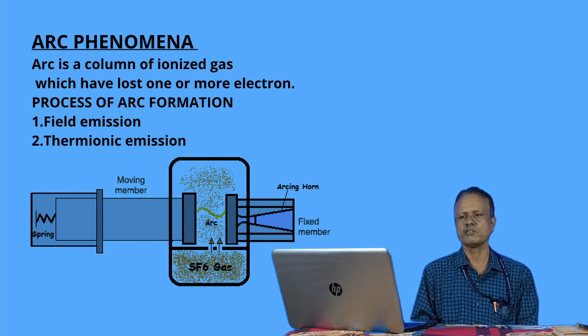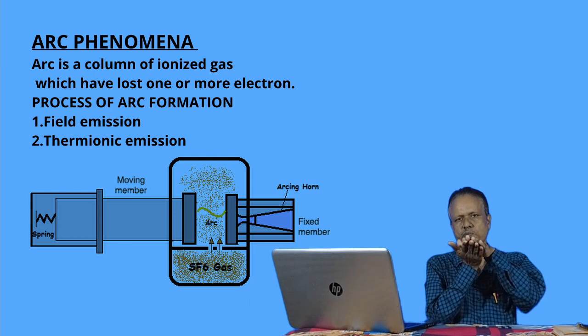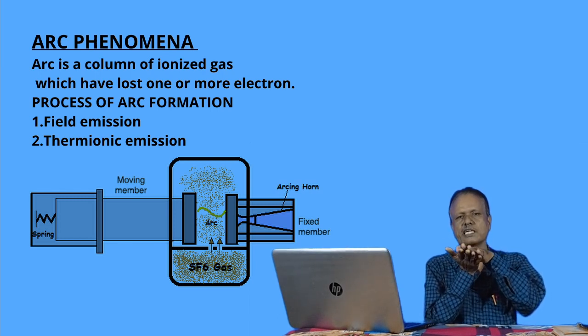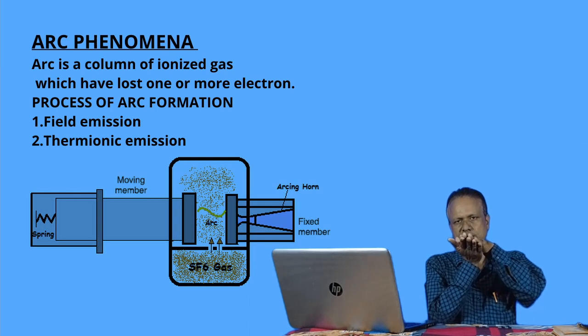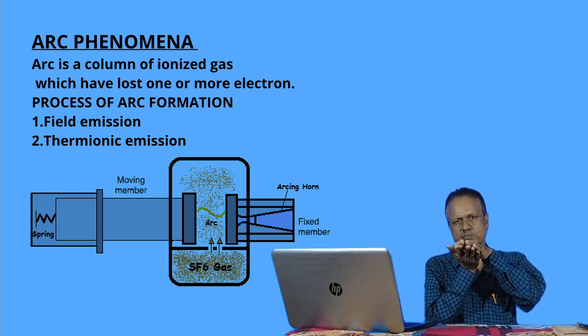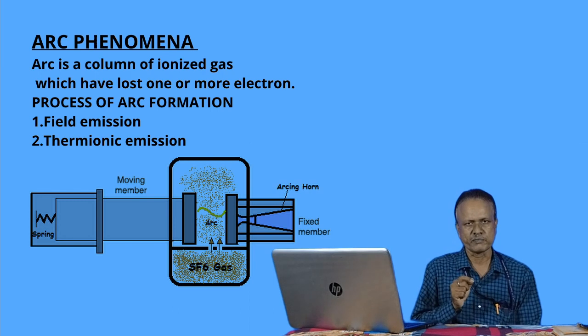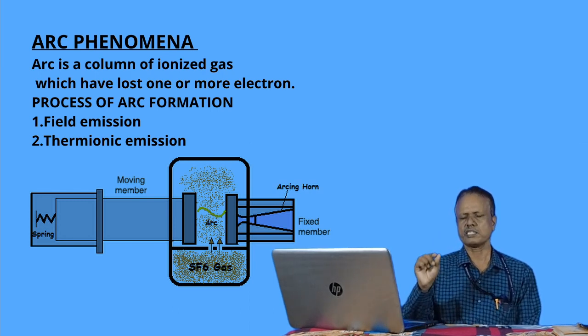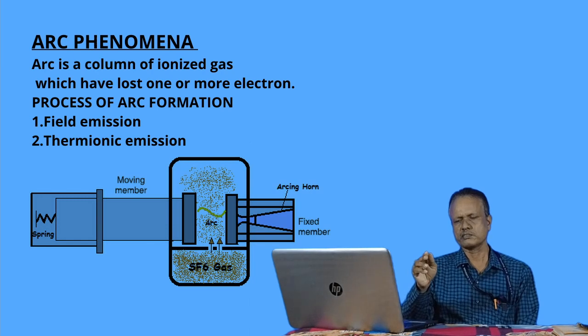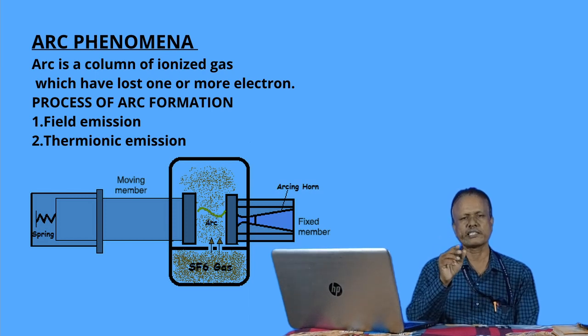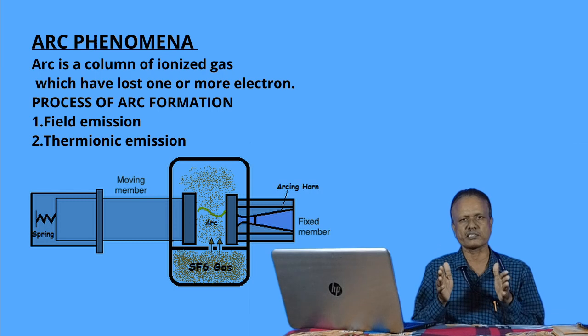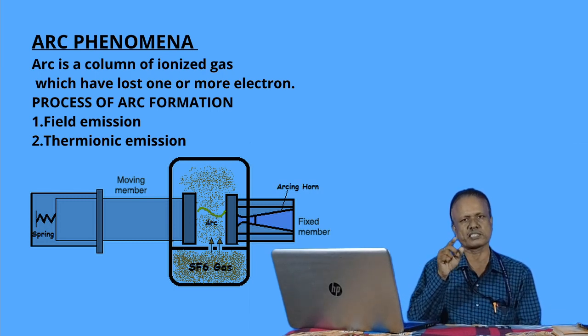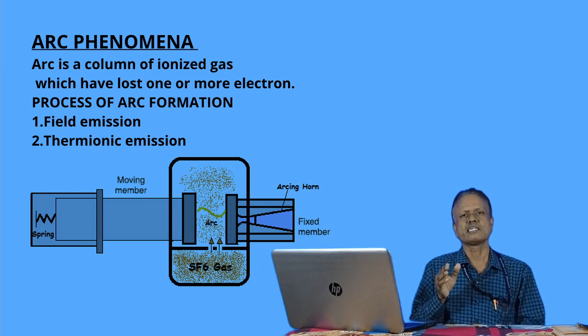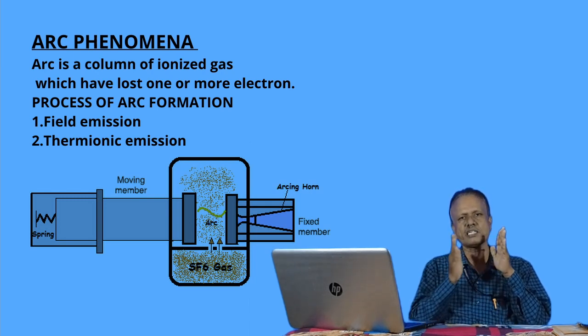In this field emission we observe that when the moving contact gets separated from the fixed contact, the contact area gets reduced, and at that time due to the reduced area we get high resistance, because R is equal to rho L by A. If the area is reduced, there is an increase in the resistance, but this resistance is very small, and due to the fault current which is of large magnitude, there is a voltage gradient of 10 to the power 6 volt per cm. So that is why it emits electrons from one plate to the other.